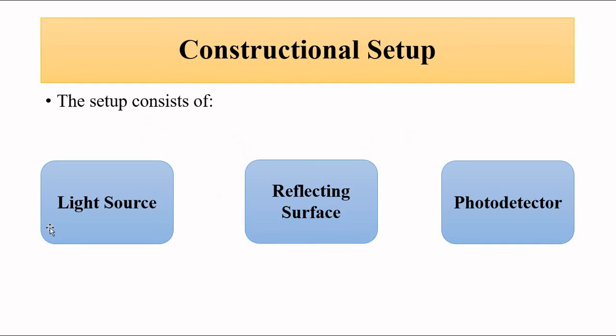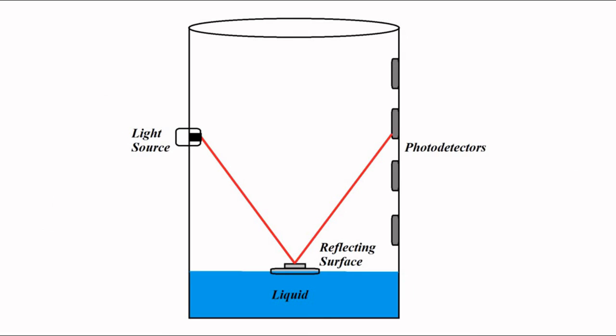This level measurement method involves an optoelectronic source — LED or laser — a reflecting surface which is a mirror, and a series of photo detectors. The signal obtained from the photo detectors can be converted into a suitable amplified signal through signal conditioning, amplification, filtering, noise cancellation, and linearization. It is then converted into a proper digital signal using analog-to-digital conversion techniques — sampling, quantization, and coding — to get a proper digital readout.